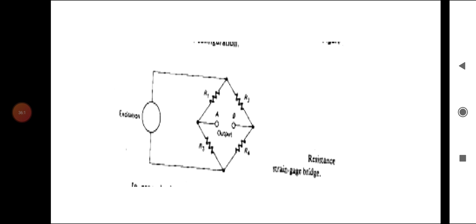Initially, with no pressure, the bridge is balanced. When blood pressure changes, the transducer resistance increases and the bridge becomes unbalanced. The unbalanced potential generated by this bridge circuit is calibrated in terms of the blood pressure measurement. Voltage appears between the terminals proportional to the pressure.